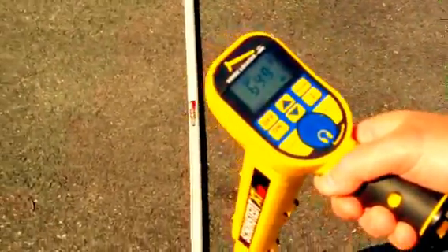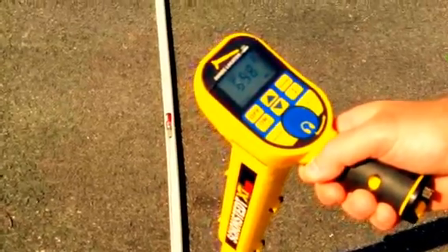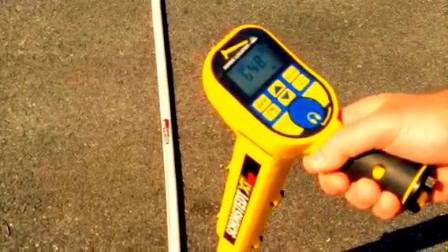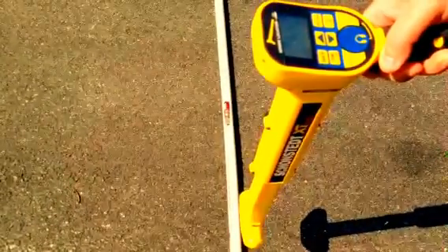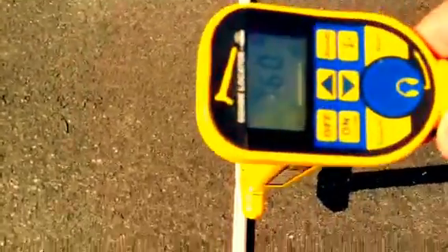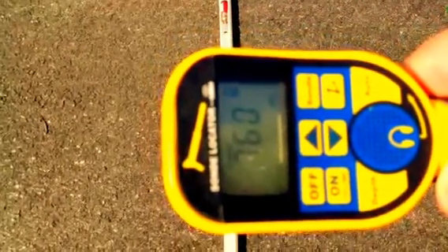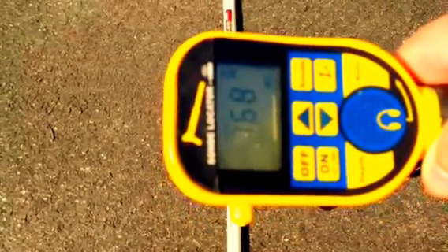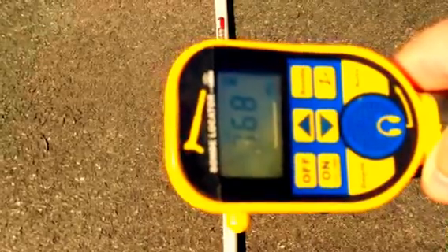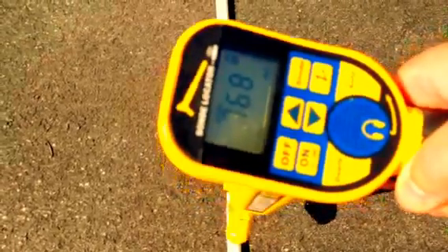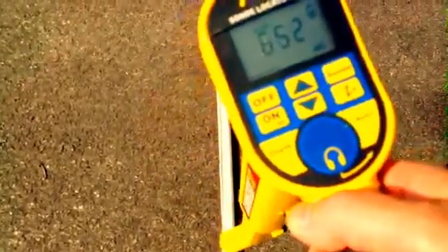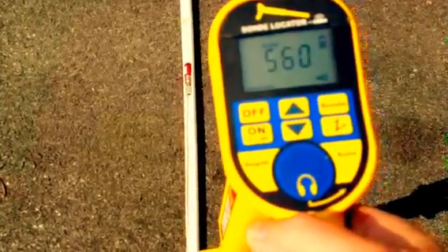The orientation of the receiver is very important. As I demonstrate now, as I turn the axis of the arrowhead tip antenna and put it in line with the beacon's orientation in the pipe, you'll notice that the signal strength increases when you're in line with the same orientation of the sonde or the camera in the pipeline. If you rotate it out of alignment, the signal strength will drop down.